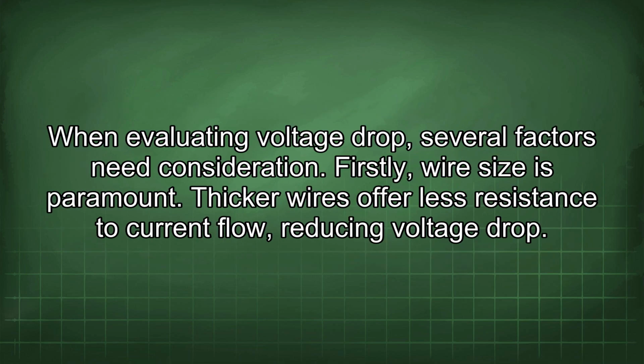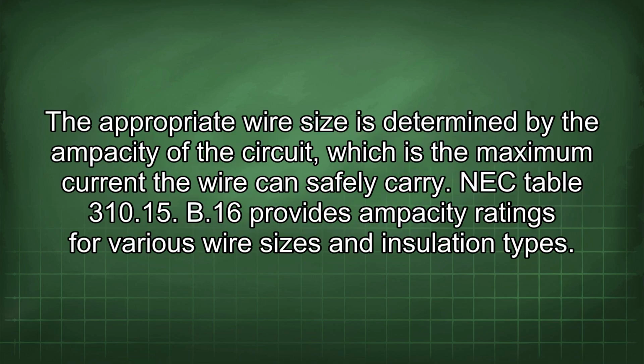When evaluating voltage drop, several factors need consideration. Firstly, wire size is paramount. Thicker wires offer less resistance to current flow, reducing voltage drop. The appropriate wire size is determined by the ampacity of the circuit, which is the maximum current a wire can safely carry. NEC Table 310.15(B)(16) provides ampacity ratings for various wire sizes and insulation types.